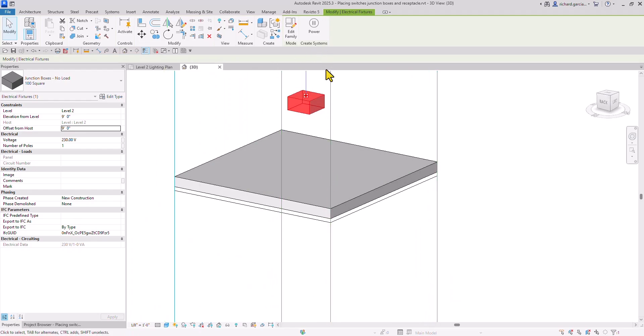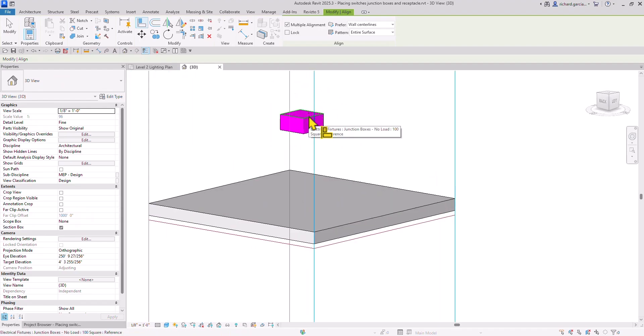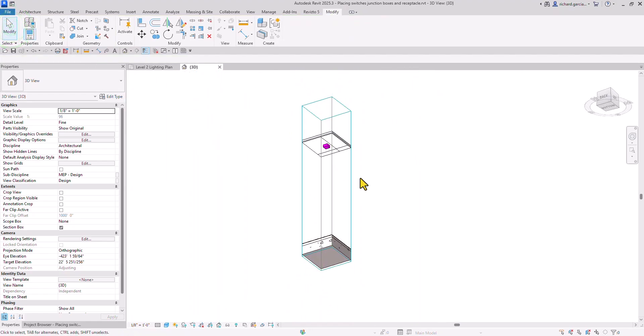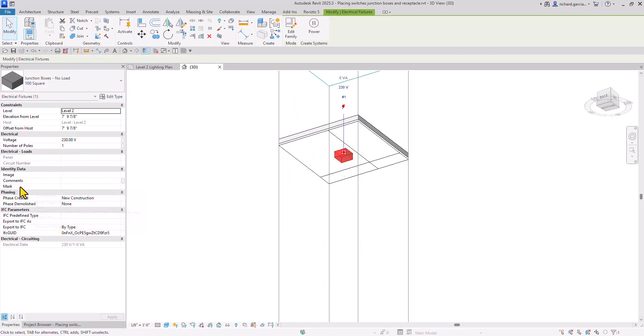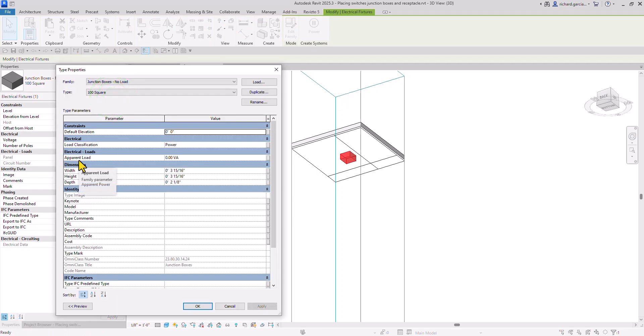You can also use the Align tool. Make sure it's selected, look for Align, click that, then select the underside of the ceiling and select the top. Then select Modify. I can also add a mark here — let's put 'JB' for junction box, 1, No Load, and then Apply. You can check the number of poles — it's 1, voltage is 230. In Type Properties under Edit Type, you can see there's no load — 0 volt-ampere — because that family is No Load.